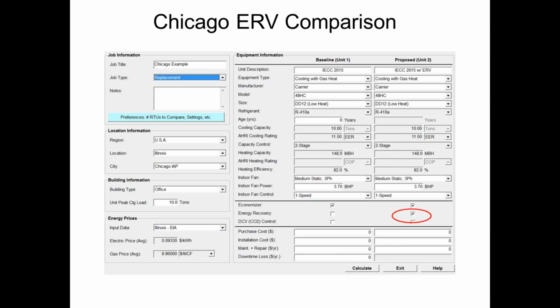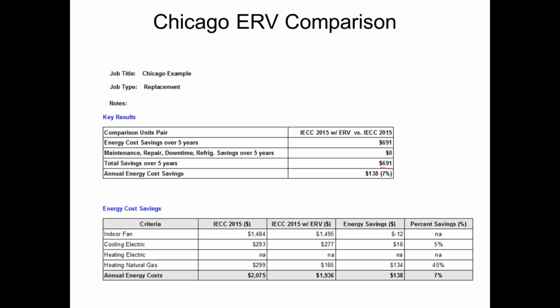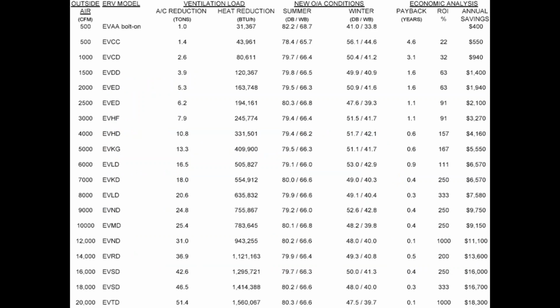Take my code example, rooftop unit, everything's identical on there. The only thing I changed is I added an ERV. And this was the potential savings for that example, 7%. Now, the ERV savings varies widely. This was 7% on this quote-unquote typical 10-ton office building we were looking at. But my savings is dramatically different for places that have lots of people, right? So like an auditorium or something like that.